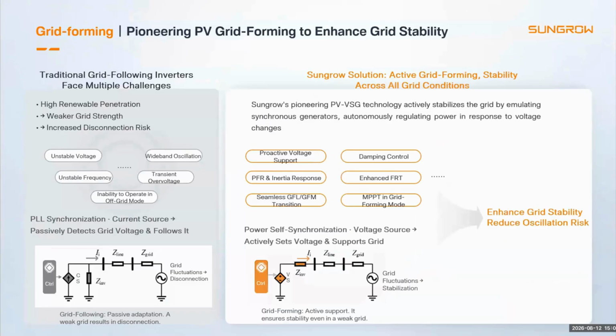Now let's look at our grid forming technology. Traditional grid following inverters detect and follow the existing grid. This works well in a strong grid, but weak grids can create voltage, frequency, and oscillation problems. Grid forming works differently. The inverter behaves more like a voltage source and actively supports the grid. Our PV VSG technology can provide voltage support, damping control, inertia response, primary frequency response, and enhanced fault ride-through. In simple terms, grid following adapts to the grid, while grid forming actively supports the grid.